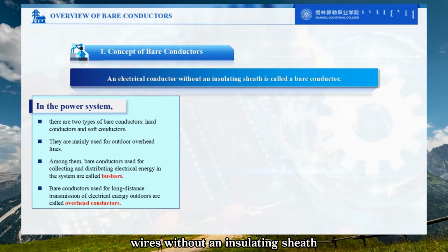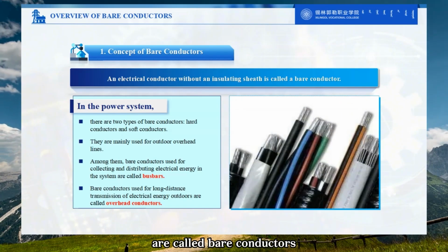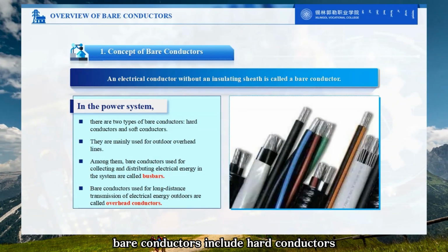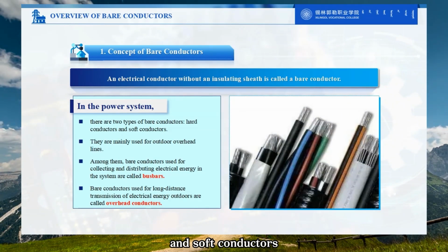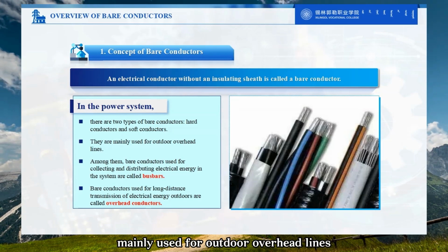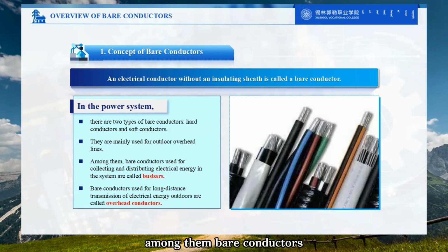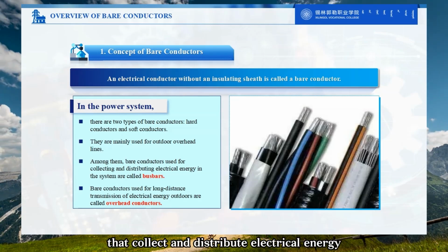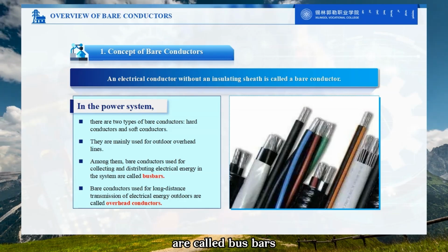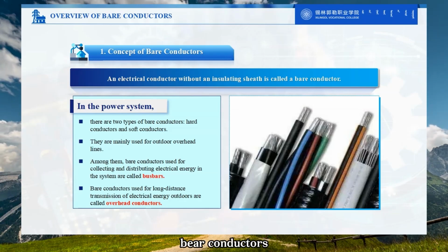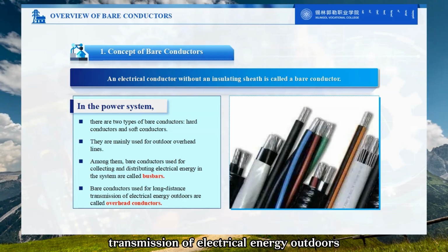Wires without an insulating sheath are called bare conductors. In power systems, bare conductors include hard conductors and soft conductors, mainly used for outdoor overhead lines. Among them, bare conductors that collect and distribute electrical energy within the system are called busbars. Bare conductors used for long-distance transmission of electrical energy outdoors are called overhead lines.